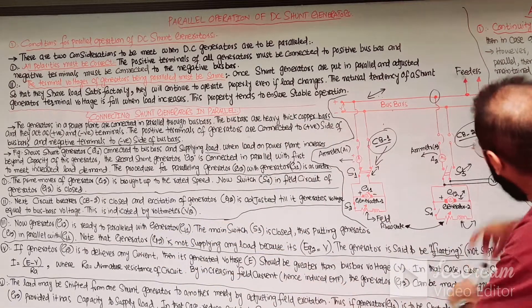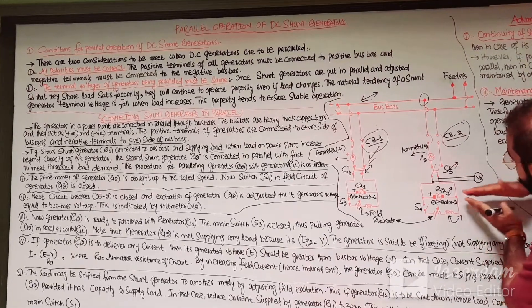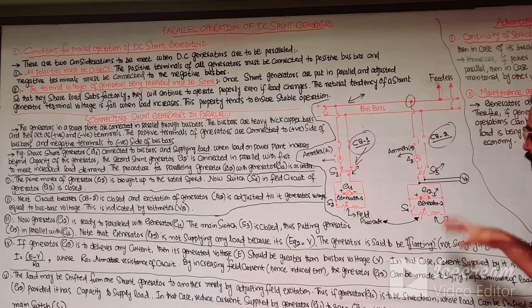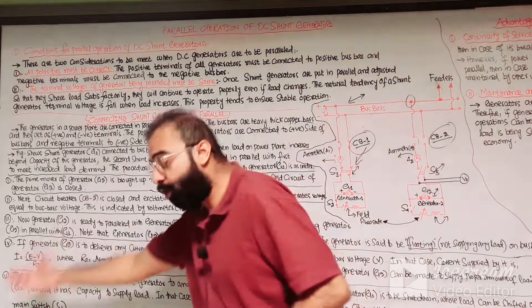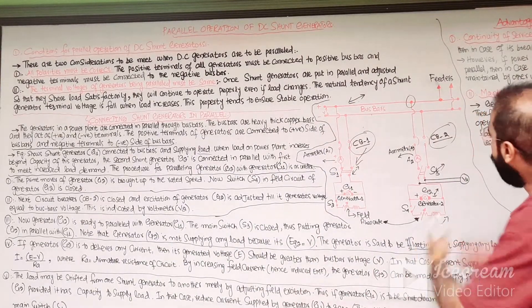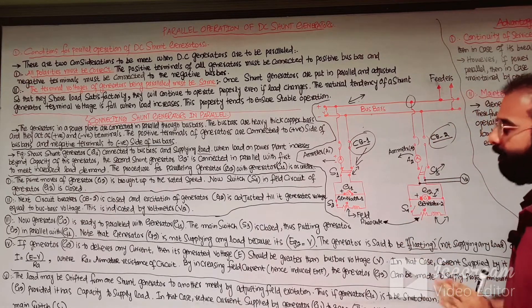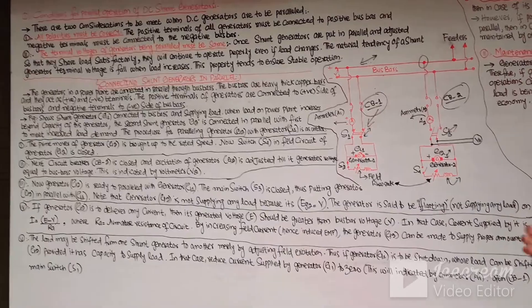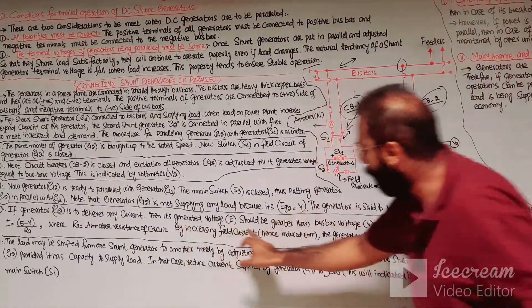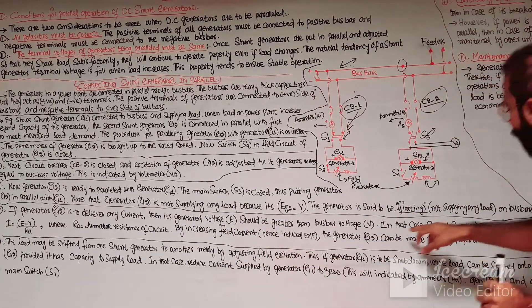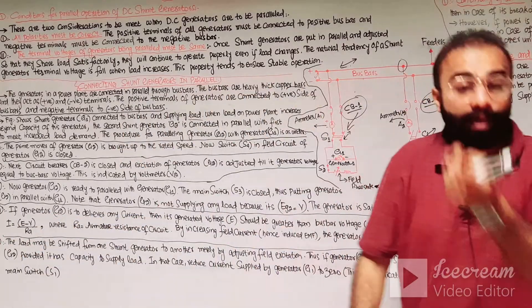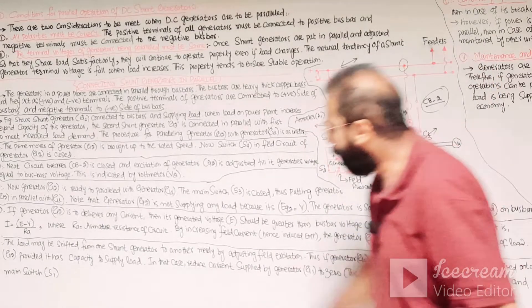In the floating state, generator G2 is not supplying any load because its terminal bus bar voltage equals the G2 generator voltage. The fourth step: if generator G2 is to deliver any current to the bus bars, its generated voltage must be greater than the bus bar voltage. In that case, the current supplied is the difference of the generated voltage and the terminal voltage divided by the resistance of the armature circuit of G2, increased by raising the field current.